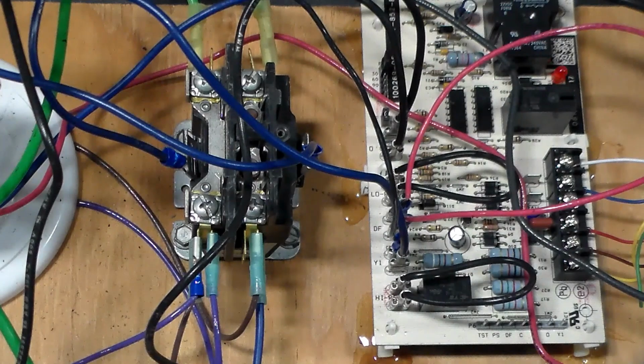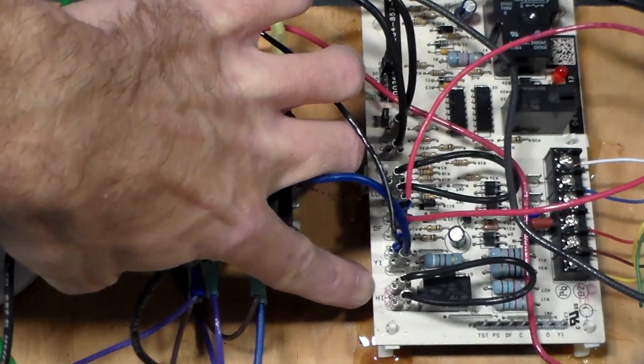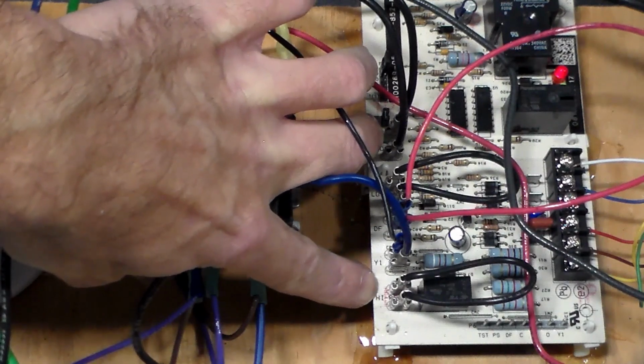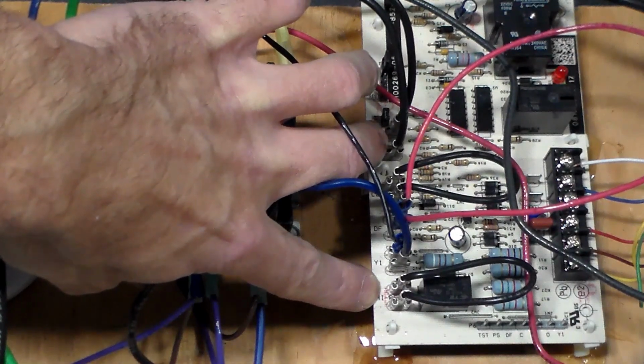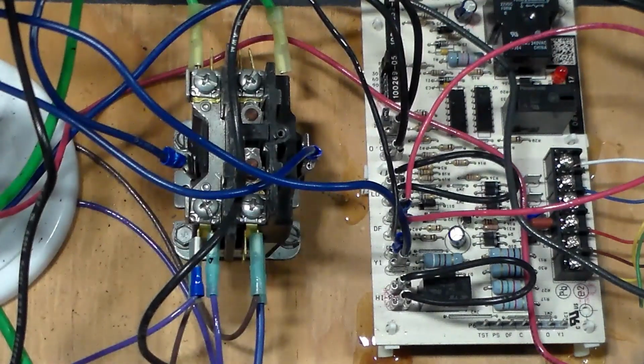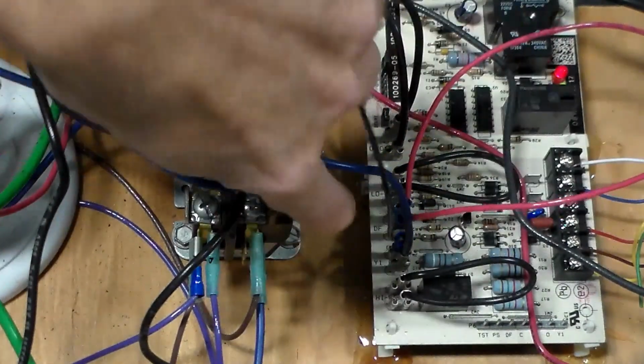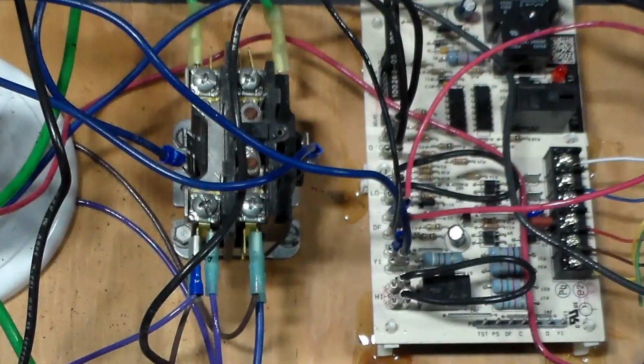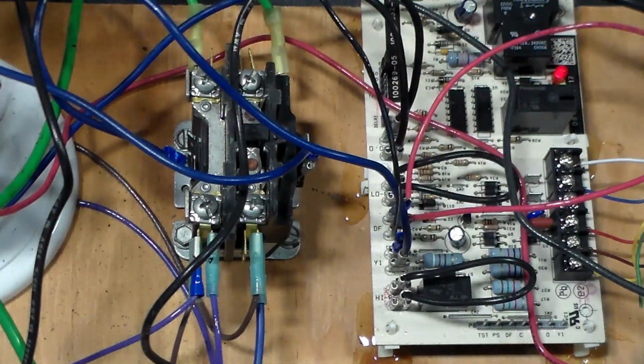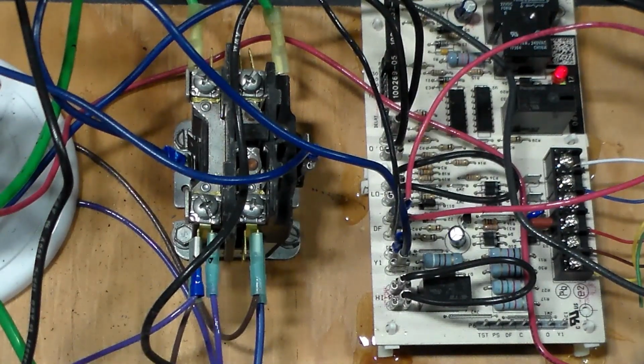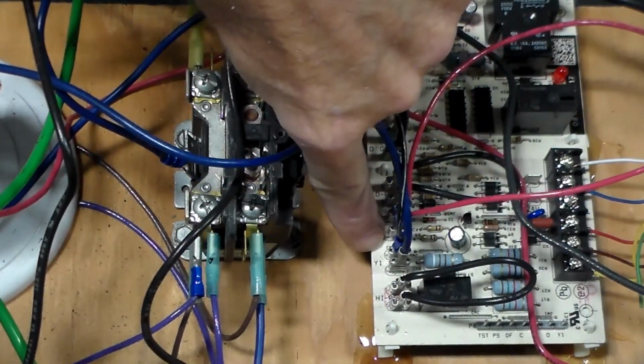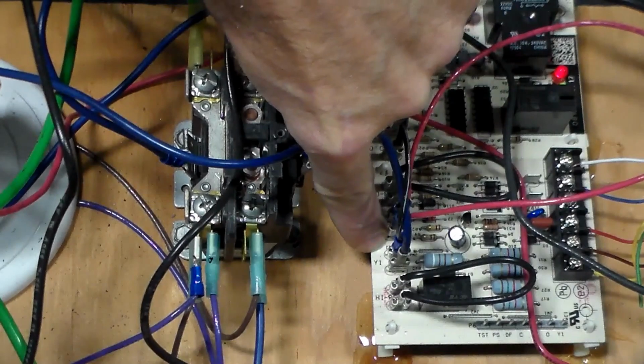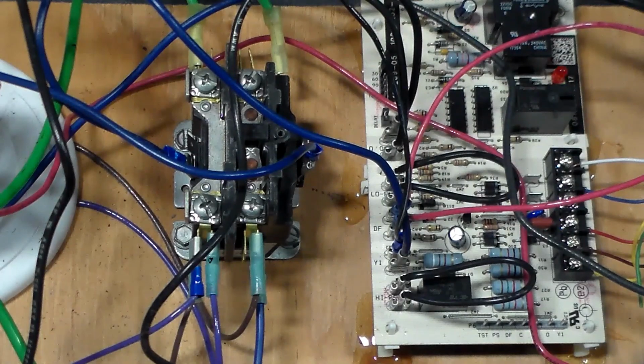First, let's talk about these terminals on the side over here. So I have, here it says high, and as you can see I have that bypassed. So that's supposed to be where a high pressure sensor, you know, transducer, thermistor type high pressure sensor would plug in there. And I just have it jumped out, so I'm tricking the board into thinking the pressure's good on the high side, right? Then I have these Y1s, and sometimes on the boards it's just labeled YY. And you can see one of them says out. In between there, I don't know if you can see it, but it says out in between these two terminals. That would be your wires that go to your contactor. So your board, when it wants to control the contactor, it's going to send 24 volts out of that Y1. And it's the top one, I don't know if you can see it on the camera, but the top one's labeled common. So 24 volt common, 24 volt hot on your call for cool out to your contactor.